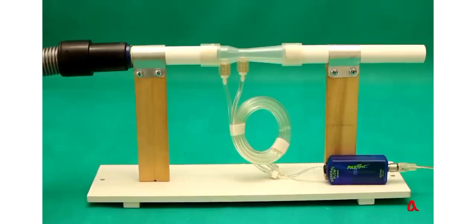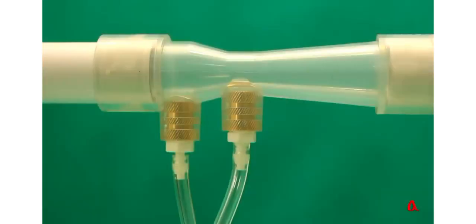This equation allows us to measure the speed and volume consumption of a gas or fluid flowing through the pipe. To do this, a special device is inserted into the pipe. It is called a Venturi tube, by the name of its inventor. A differential pressure sensor is attached to the tube. It measures the difference of pressure between the narrow and the wide sections of the pipe. The speed of flow calculation is based on this difference.